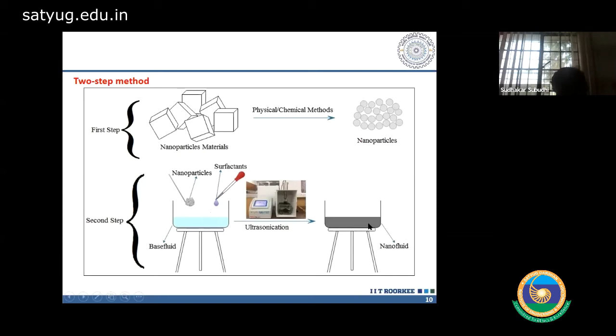So next is characterization of nanofluids. For this, you have to measure different thermal properties. In this case, we are measuring thermal conductivity using a KD2 probe imported from Decagon Devices, US. We are also using another instrument, a thermal property analyzer, imported from Sweden. Then we are measuring viscosity using an MCR 103 rheometer imported from Austria. For stability analysis, we are using a Zetasizer imported from the UK. And for SEM analysis, a scanning electron microscope can measure the actual diameter of the nanoparticles. We are using the SEM microscope that is available in our instrumentation center.